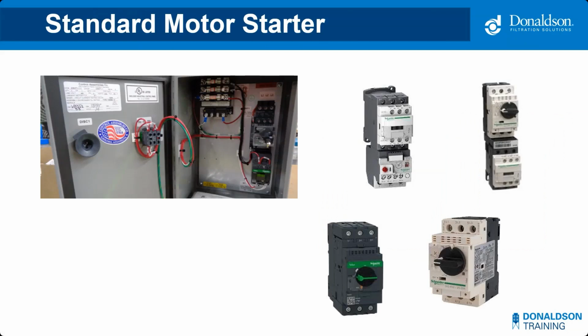Thank you, Asa. We have 3 general categories of fan blower motor starters: a standard motor starter, a soft starter, and a variable frequency drive. So when would you choose just the basic standard motor starter option? When you want the controls to be plain, simple, and cost-effective. Motor starters and manual motor protectors are often referred to as a starter, an across-the-line starter, or a direct online starter. A starter is simply a contactor plus an overload. The contactor will receive a signal from the start button, and it'll close the contacts for the circuit to turn the motor on.